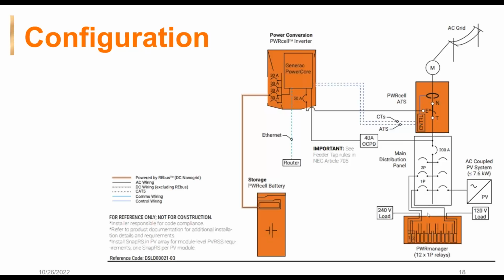The thing I want to be clear about is the power manager: you're backing up all of the loads that are connected in the main service panel in addition to the loads in the power manager. We've had some installers think maybe they're just backing up the loads in the power manager, or they're using it without an ATS in some configurations. No, you're backing up the entire main service panel and the loads in the power manager, but we're going to manage the loads that are connected to the power manager.